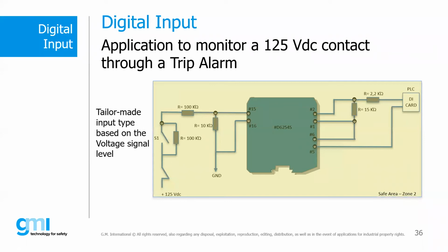Of course, diagnosing a wet contact in the field is difficult. How is it possible to understand and differentiate the closed state of a contact from a short circuit, for example? And again, how can we distinguish between the open state of a contact and an open circuit fault? This condition makes us think that diagnosing a wet contact from voltage in the field is impossible. But GMI, through one of its analog devices, has studied a possible solution to overcome this type of problem and be able to provide diagnostics of a wet contact in the field.